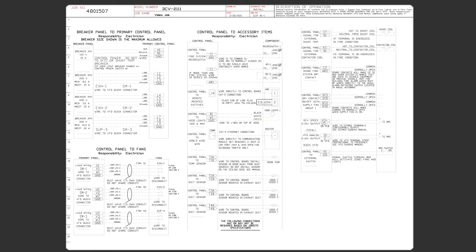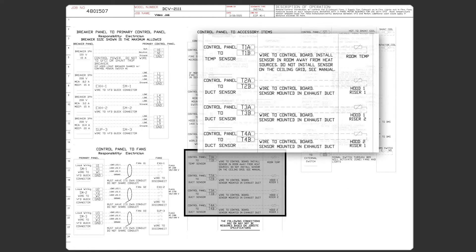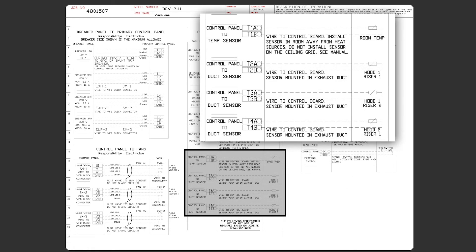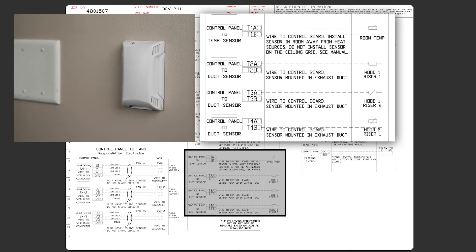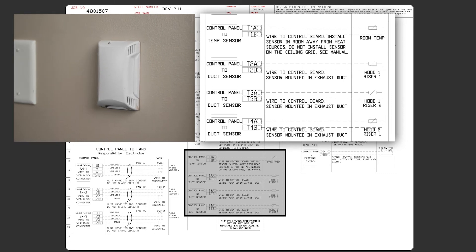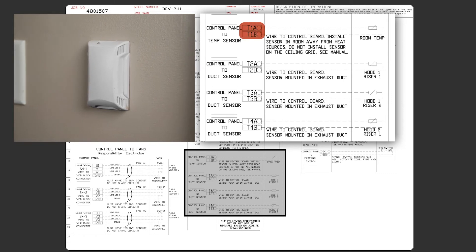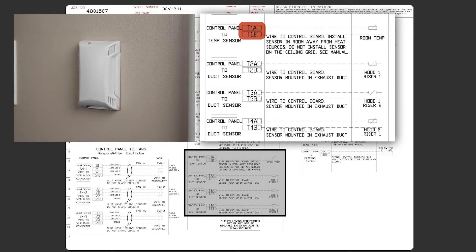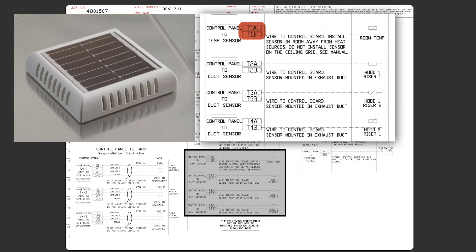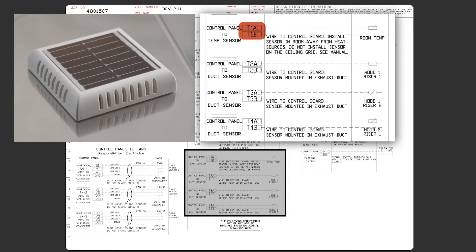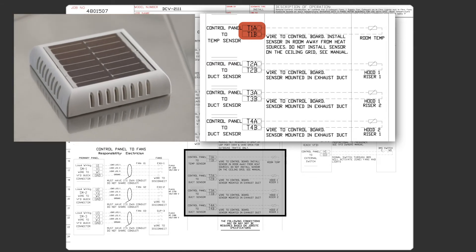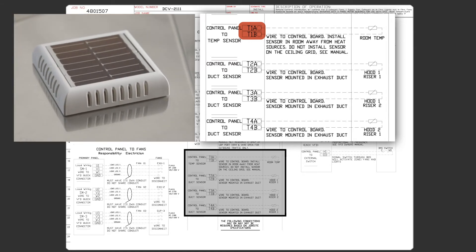First, let's look at the wiring diagram. Each temp sensor is listed on the diagram along with its location. The first sensor will always be the room temp sensor and will be wired to terminals T1, A, and B. Unless your system is using a wireless sensor or a preset room temperature, there will be no wires on the T1 terminals.